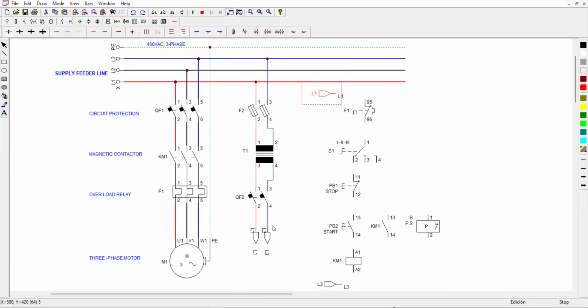This will be our source. The function of this is an input source from our circuit breaker QF2. Okay, let's connect our circuit. I will use the red connecting wires here. Since this is a red line 1, it is very easy to trace up. It's line 1. And of course, I would rather use this block as our connection. The block, of course the block. And we'll connect our auxiliary contact parallel to our start push button.